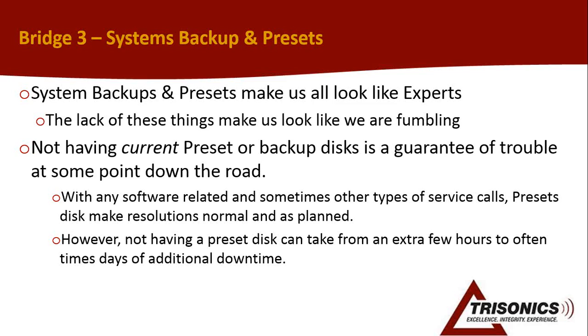And it's one thing if we come in and we never knew the ultrasound machine was there and something happened and it's a new situation. But if we've been servicing that unit, or you guys have had that unit under your care for a long time, and the unit loses a hard drive or the software needs reloaded, and we don't have the system options to load back in, or the presets to load back in, or the IP addresses to put back in, it can delay a service call for at least hours. And I've actually experienced days of downtime over these types of things.